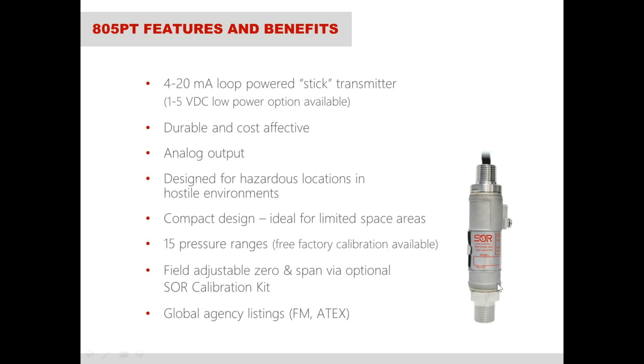It comes in a solid 316 stainless steel housing. It's a cast housing. It's very durable, thick, and strong. You can drop it on the ground. You can put wrenches on the actual housing and tighten it down, and you won't damage the actual housing. As opposed to some of the other stick transmitters out there that are kind of flimsy and small and can break pretty easily. Very compact design as well. It is about 6 inches tall, so as compared to a Rosemount 3051 or your traditional style pressure transmitter, the footprint that it consumes is a lot smaller than your traditional style.